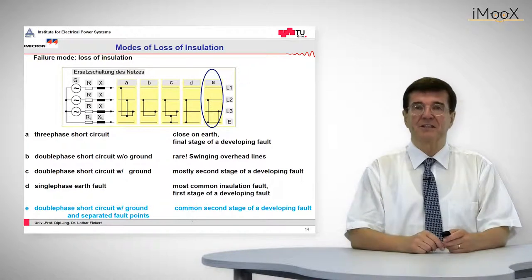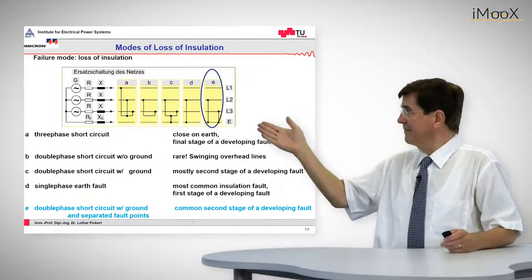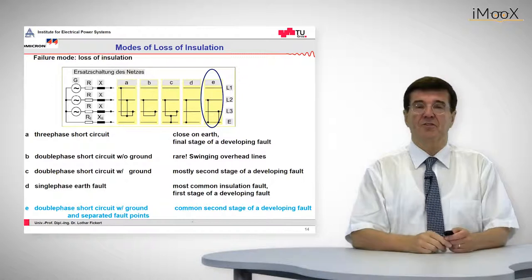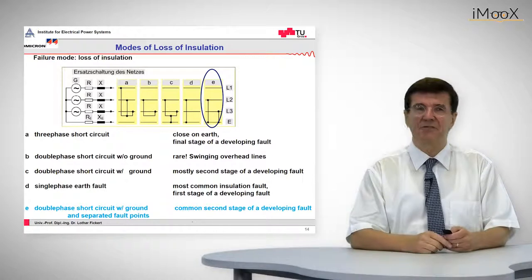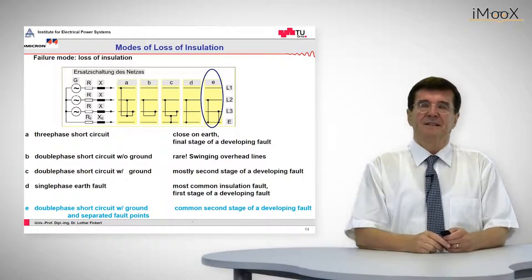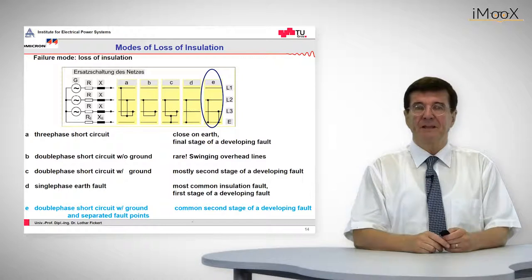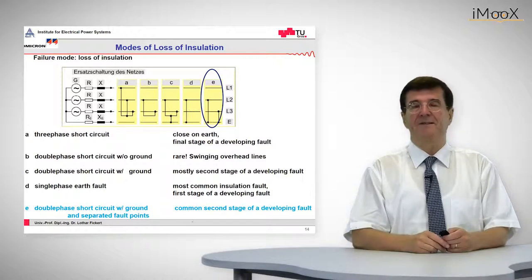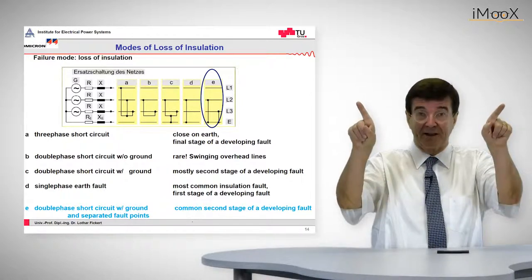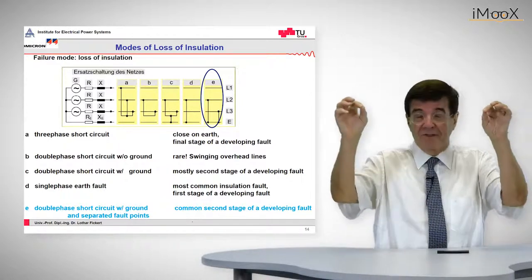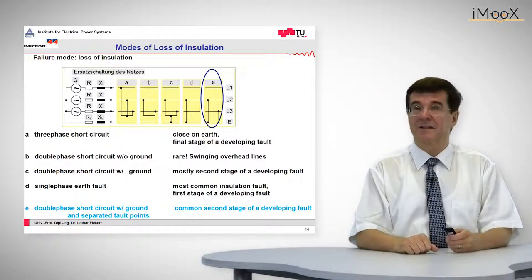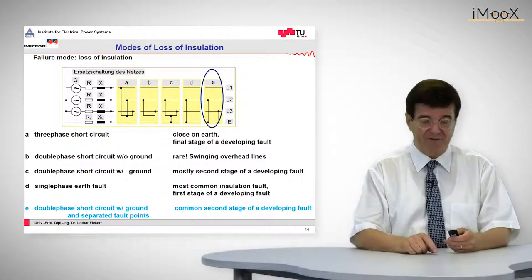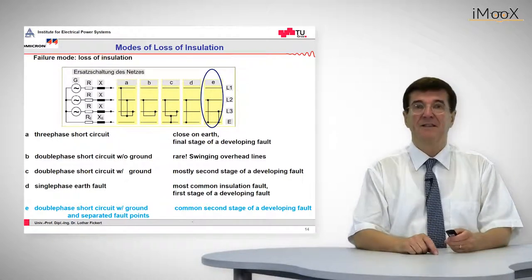The last fault, classified here as E, is the so-called cross-country fault. This is a double ground fault in two different phases. This situation occurs in many cases in the aftermath of a single-phase to ground fault, where due to the increase of voltages in the healthy phases, one of those healthy phases experiences another voltage breakdown — a second fault point in the grid at some other location and in the second phase. So this is called the cross-country fault.